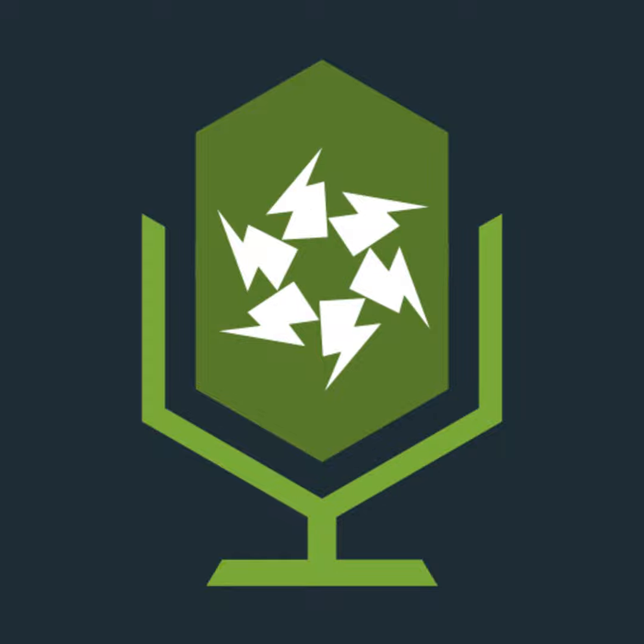Final circuits means a circuit that then reaches a final point of utilisation. So this is not a distribution circuit. So if I'm going to install a circuit from the house going down to the shed where there's another fuse board in there, that's not this. If it's a circuit, let's say within the shed, going to lights or to sockets, or in the house going to the shower or the cooker, these are final circuits.